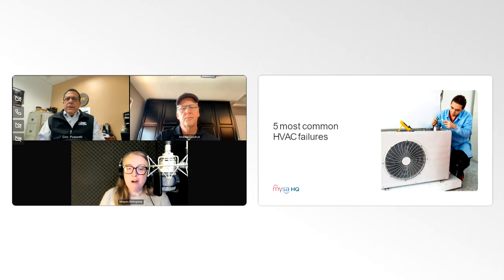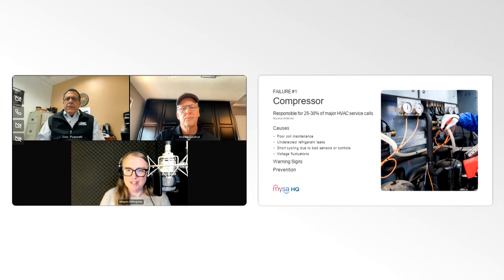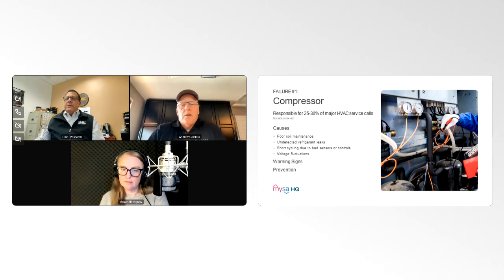We'll start with the most common source of HVAC problems, the compressor. On the slide, you can see a couple reasons why compressors fail. So Andrew, what are early warning signs that facilities managers can look out for? For sure. Typically a telltale sign of compressor failure is, whether heating, if it's a heat pump, or AC, you are going to feel that impact in temperature, whether heating or cooling.